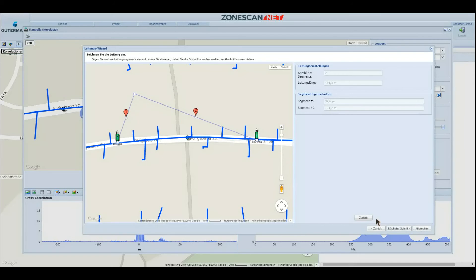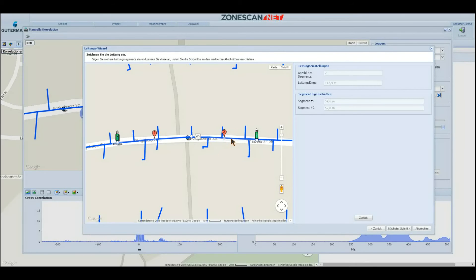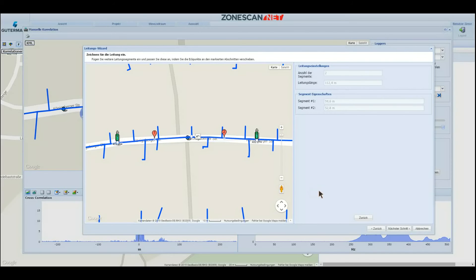Going back is as easy as well. The pipe is now laid out according to the KML file, corresponding to the connection between the two loggers. As you can see, I can click on the pipe and retrieve detailed information. In this case we are dealing with a 100mm grey cast iron pipe. The system automatically obtains the length of each segment. In this example, there are 112.4m overall between the two measuring points that are picking up the same noise.